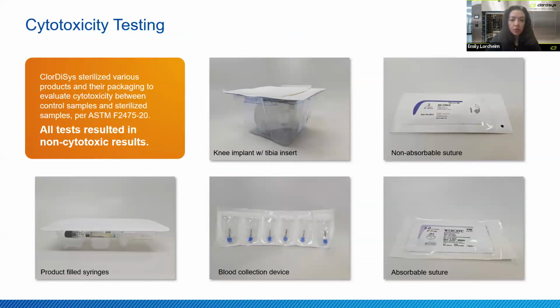Now we're going to talk about cytotoxicity testing. So not only do you need to evaluate the biocompatibility of the device itself, but following ASTM F2475-20, you also need to evaluate the cytotoxicity of the areas of your packaging where the device touches. So we did a broad sampling here of different packaging types and seeing if they were cytotoxic.